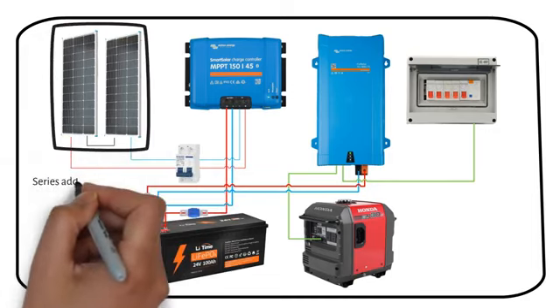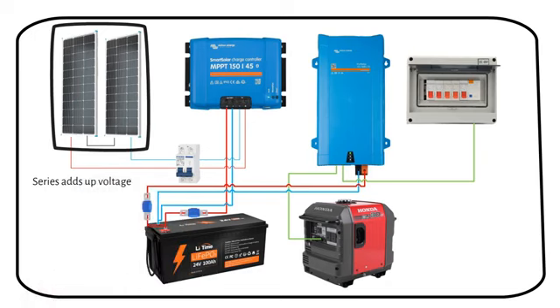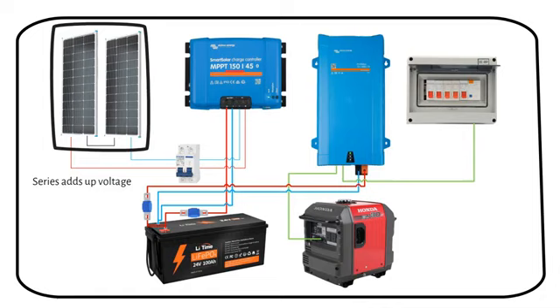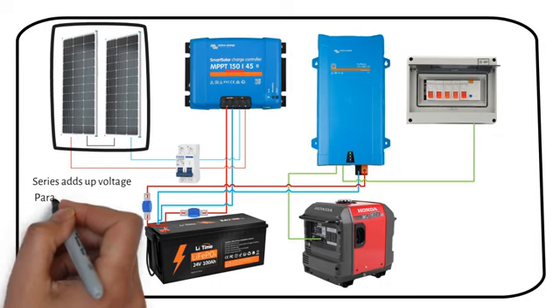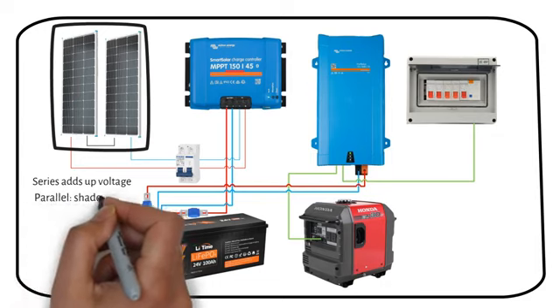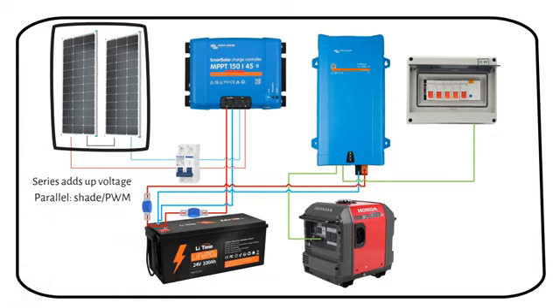We have two solar panels connected in series. This adds up the voltage while the current stays the same. It's still under the 150 volts input limit of the charge controller. Wiring the panels in series will reduce the voltage drop, so you need less thick wires to cover the long distance. Wiring in parallel is a good idea only when you have shading or use a PWM charge controller.